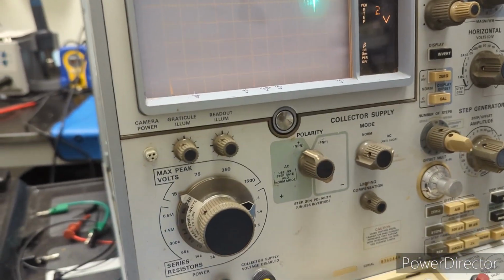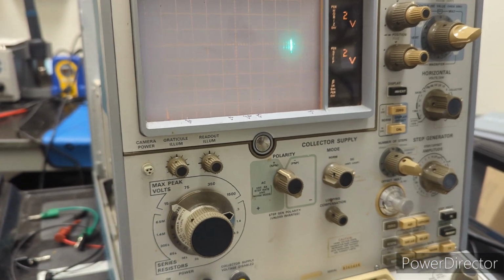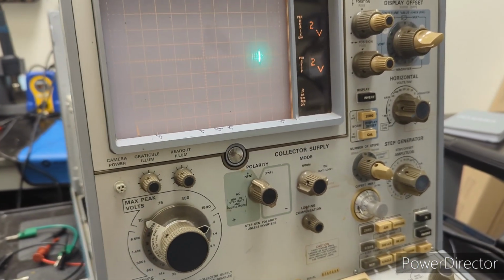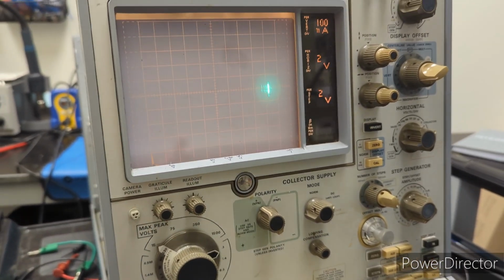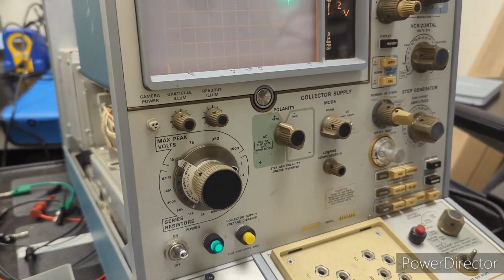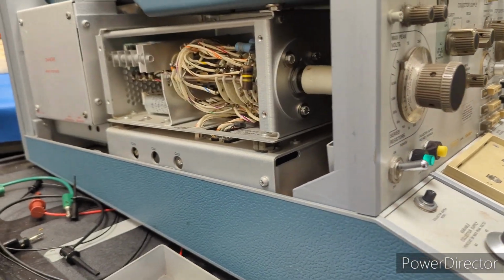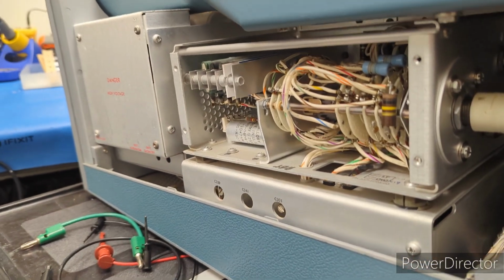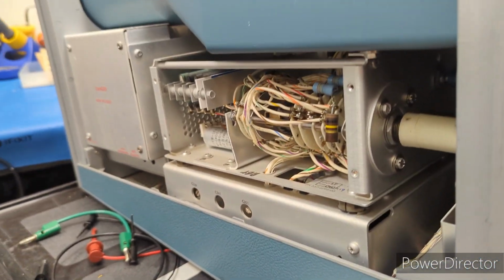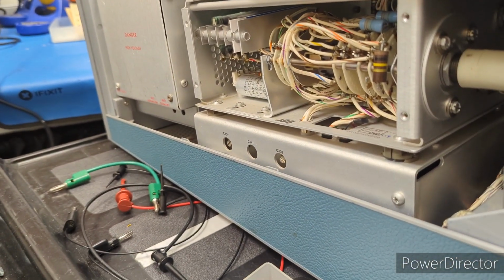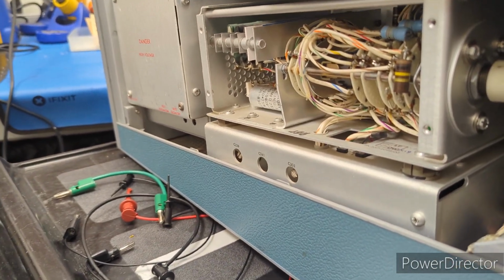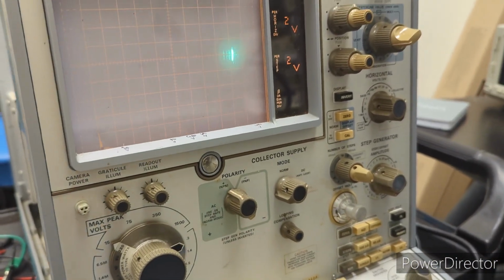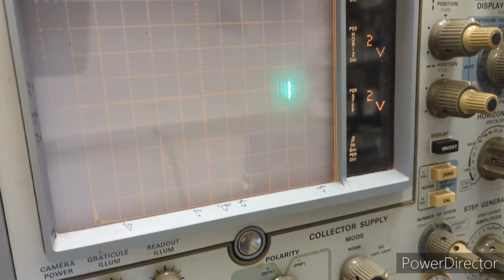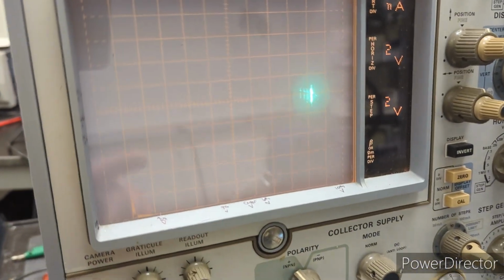Okay, so now we're on to adjusting the looping compensation. This looping is an artifact that's intrinsic to the instrument. It's caused by unwanted stray capacitance due to some components within the instrument, such as the guard box and the collector transformer. This capacitance is transferred to the chassis ground, but it's also picked up by the vertical amplifier of the instrument. The service manual tries to go in depth on how this is caused, and I still don't completely understand it, but it basically shows itself as a loop on the display.